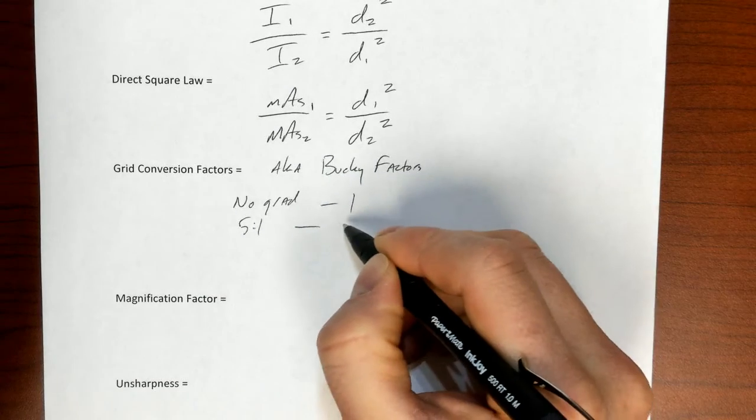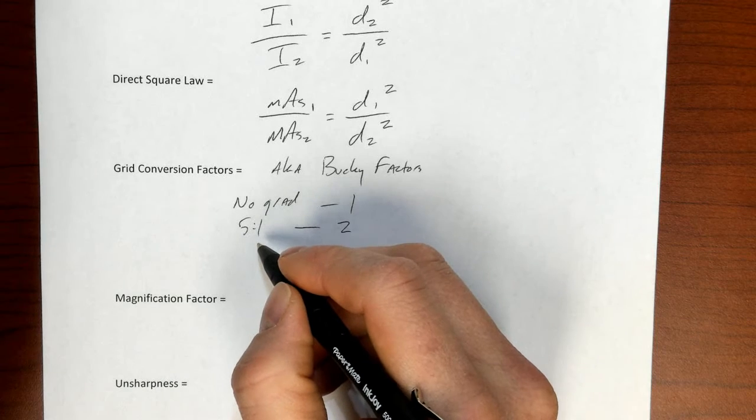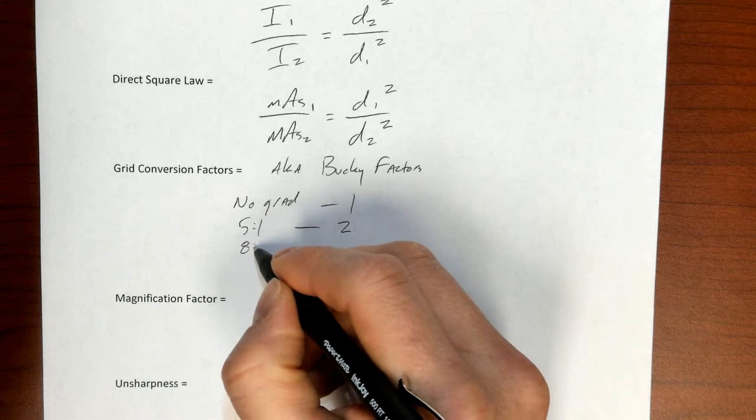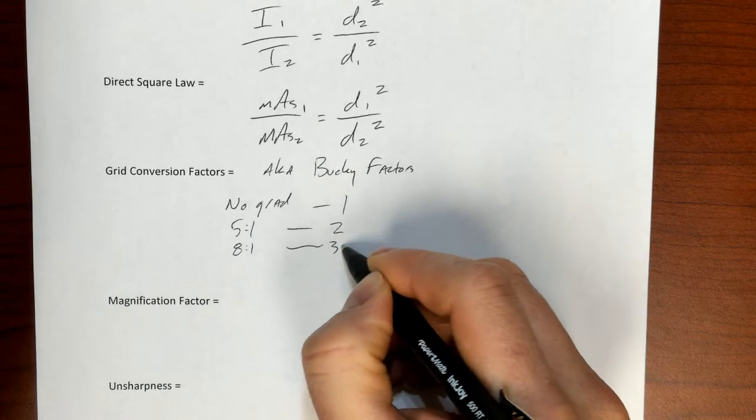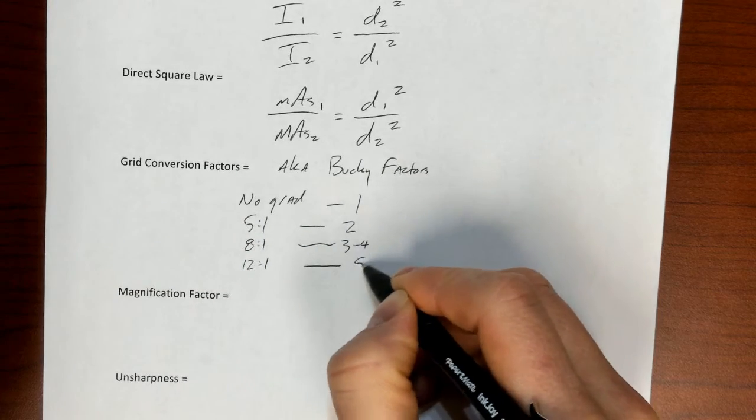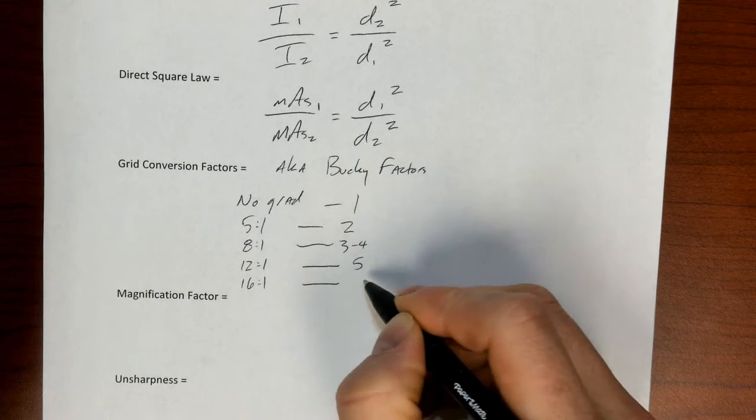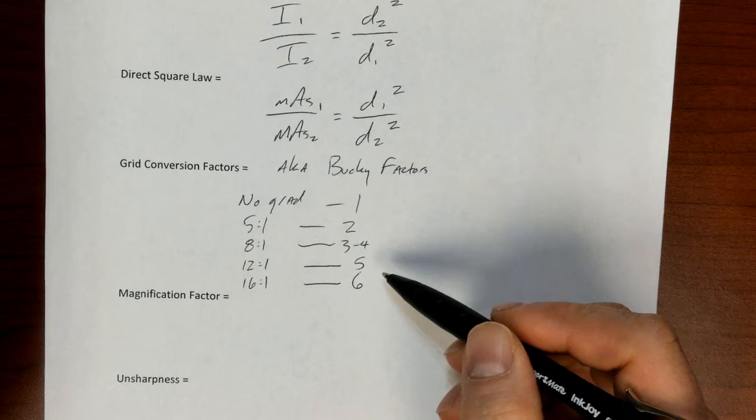And this is generally the way that I break this down. Because I'll show you, this comes from Stuart Bruchon's book. So if I'm using a 5 by 1 grid, the grid factor I need to use is a 2. An 8 by 1 grid, I would use a Bucky factor of 3 or 4. A 12 by 1 grid, a Bucky factor of 5. And a 16 by 1 grid would require an increase of mAs by about 6 times.